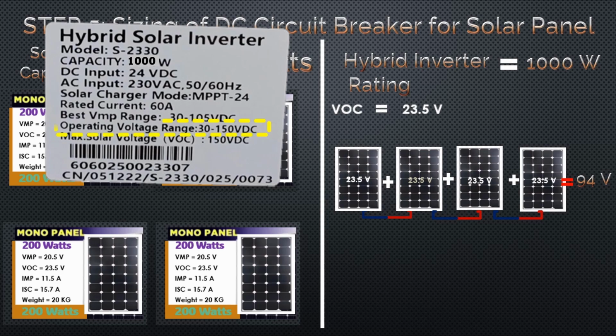Since we decided to use 4 panels in series, the next thing to do is to look at the short circuit current or ISC of the panels, because that will be your reference in sizing the DC circuit breaker. If we look at the nameplate of the solar panel, it has a short circuit current of 15.7 amperes per panel. Please note that in series connection, the current flowing in the circuit is the same at 15.7 amperes. So to compute the rating of the circuit breaker, you will add to the value of ISC a 25% safety factor as per Philippine Electrical Code.